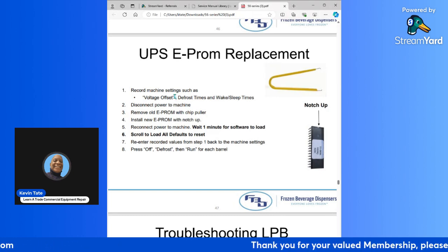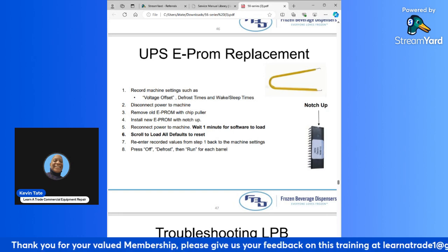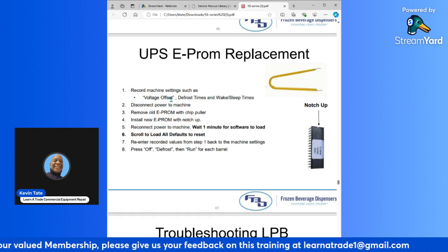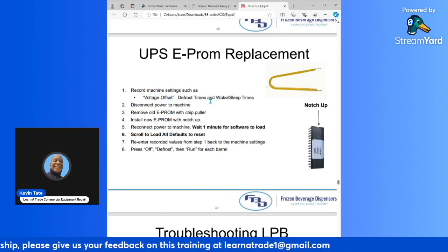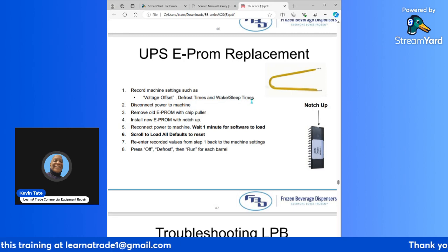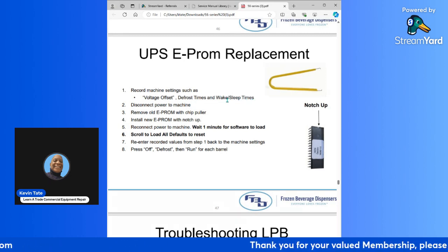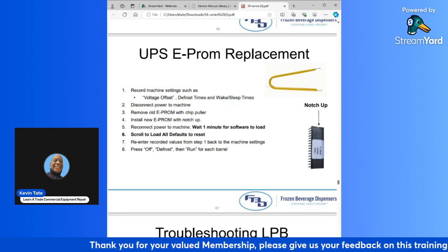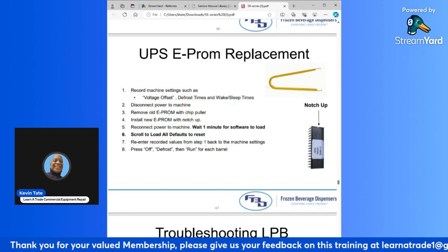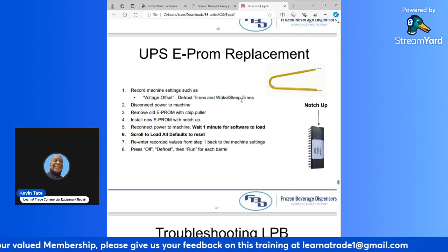This is where you would go into the service menu, then go to readouts. You could go to common, and then you would be able to see your voltage offsets, your defrost times. You can go through the menu to get your defrost times and your wake up and sleep times, if there's any stored. Like I said before, most cases these locations are usually 24/7, so they usually have no wake up or sleep times set.